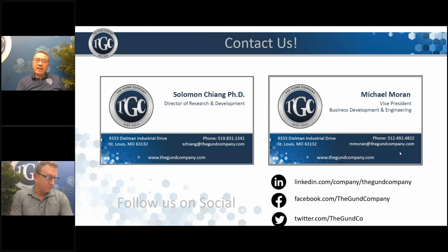Okay. Tear and flex are not part of the UL 746B diagnostic test for mechanical. I think for mechanical they use tensile and impact, but there's nothing that stops us from using the methodology of SAM 46B and doing the thermal aging against a known reference. Then we know that will perform well as far as cracking or tearing is concerned.